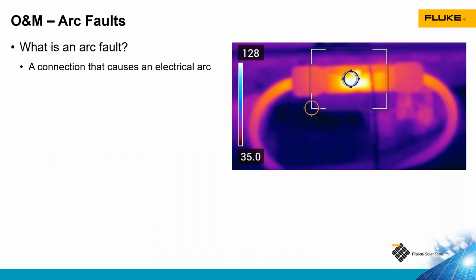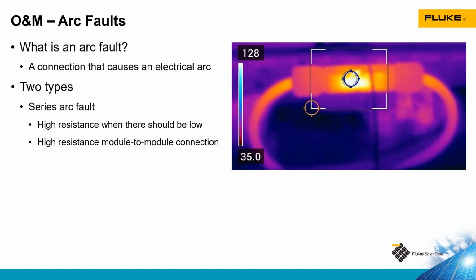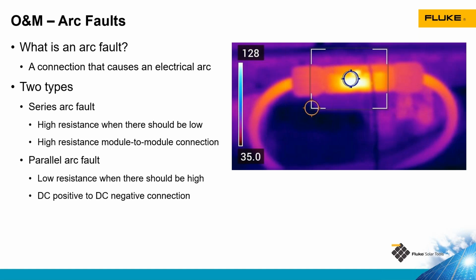Another problem we get with solar installations are arc faults. An arc fault is a resistance connection. There are 2 types of arc faults. There's a series arc fault, where I have high resistance in a circuit where I want low resistance. An example could be the module interconnection we see here in the picture. We've got a positive and negative connector between 2 modules. Something is wrong with that connector. Either it wasn't plugged in all the way, or it was damaged, or they got some kind of corrosion or mud inside the connector, or they made a connector in the field and did a bad job making that connector up. And something in that connection is arcing and causing increased resistance. I don't want that. I want low resistance.